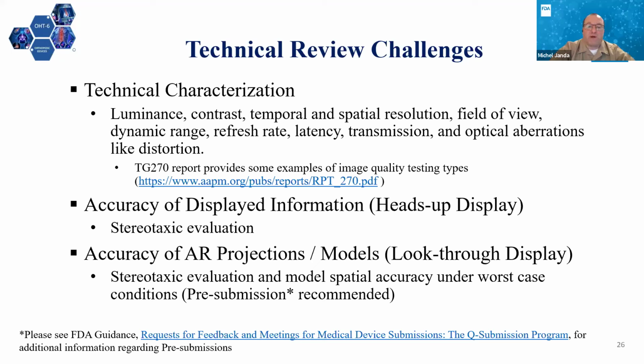As the AR system cannot impact upon the displayed information, when intended to provide additional 3D projection or models corresponding to the navigation data provided by the primary stereotactic system, medical AR developers are asked to provide additional quantitative validation of the projected model's spatial accuracy under simulated worst-case conditions. Developing a validation protocol for 3D projections and models is challenging, as these virtual models are intended to be observed and interpreted from the user's perspective.